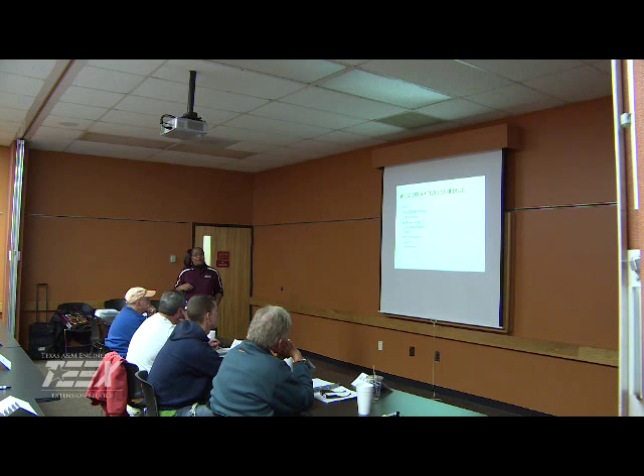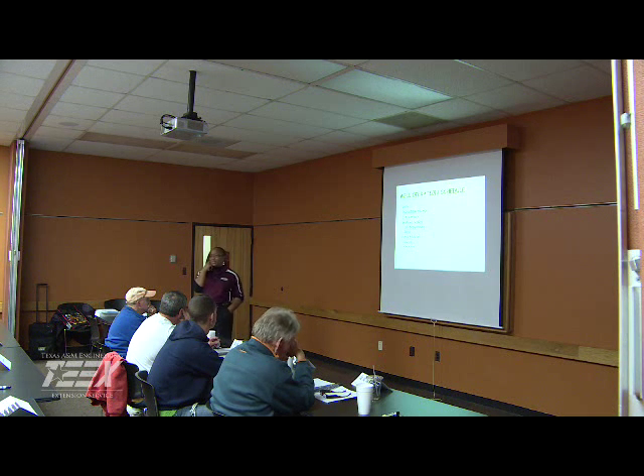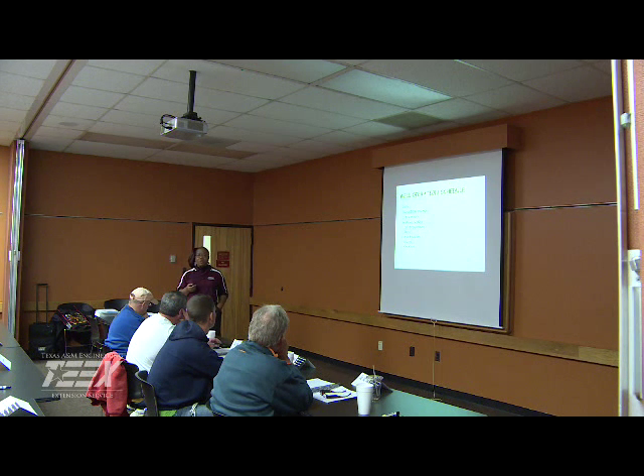Pump and motor, you want to use your eyes and ears and nose. In other words, when you come to a site, make sure again, am I hearing unusual noises? Is there a clicking, a chattering, what have you? Do I smell something burning? So use your senses in order to determine whether or not you have new or different things occurring with your pumps or motors.